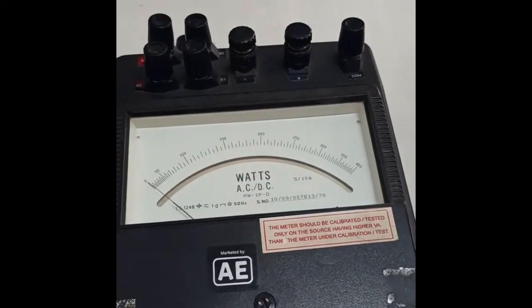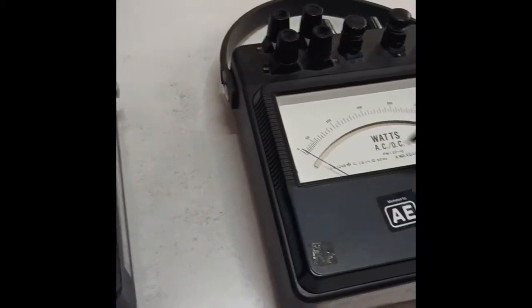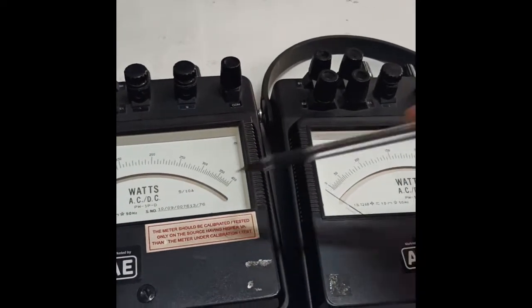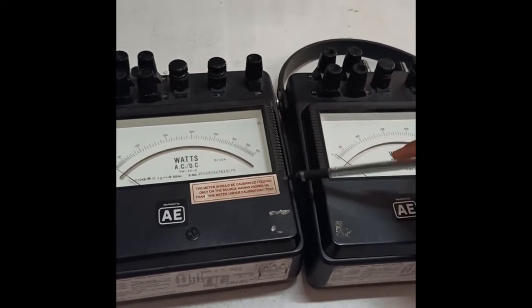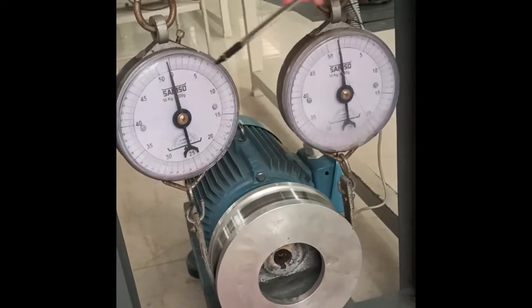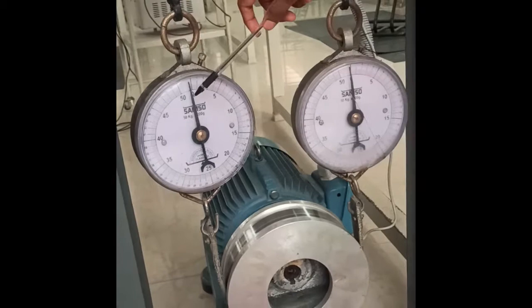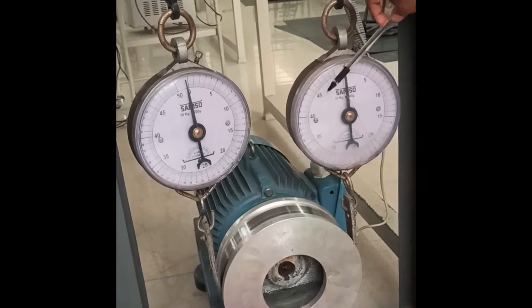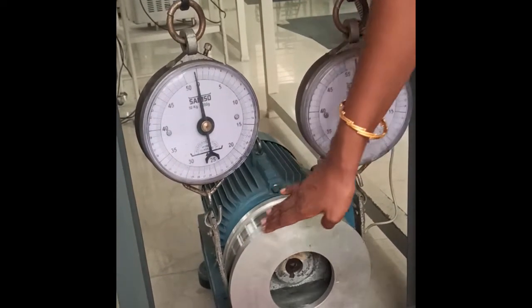Then we are using the 2 wattmeter method here in order to measure three-phase power. So we have two identical wattmeters, W1 and W2. These are unity power factor wattmeters. And then to load the given motor, we are using a belt and a brake drum arrangement. And these are called spring balances. Initially we have to adjust the weights or the scale to 0. That is, the rotor should be free for rotation.